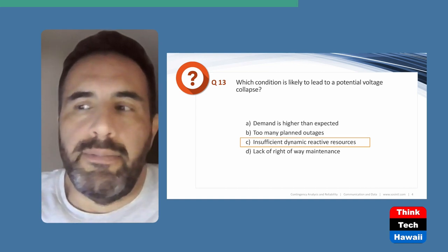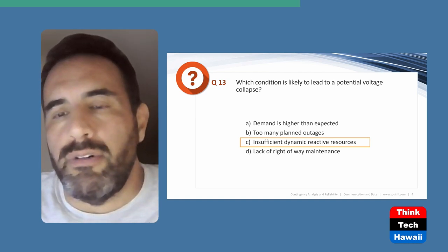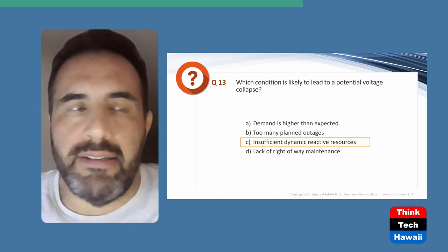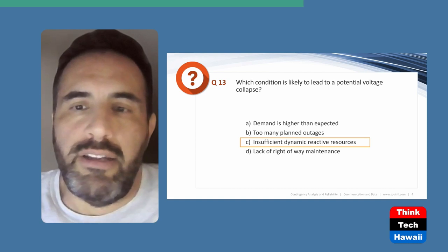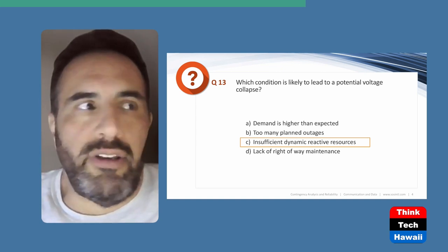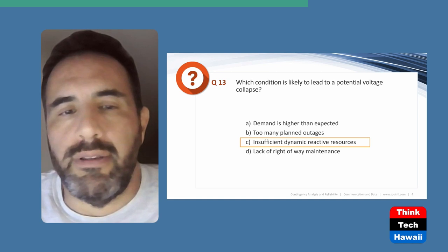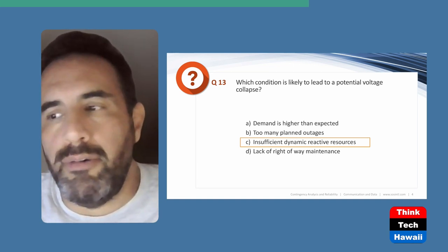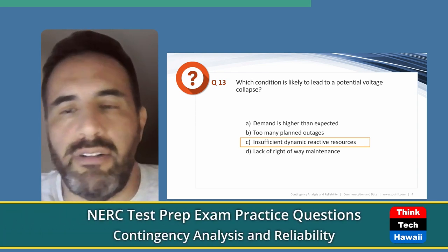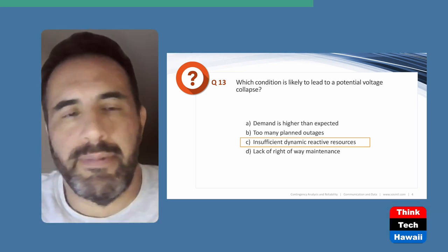Once generators can't provide more reactive support, you rely on cap banks and capacitors — but those are static resources, very finite. If you wait too long to switch them in, you reduce their capability. Static VAR compensators and synchronous condensers are great dynamic reactive resources, but if you run all of those to their limits and load continues to climb, you will have trouble supporting voltage. Insufficient dynamic reactive resources leads to voltage collapse.